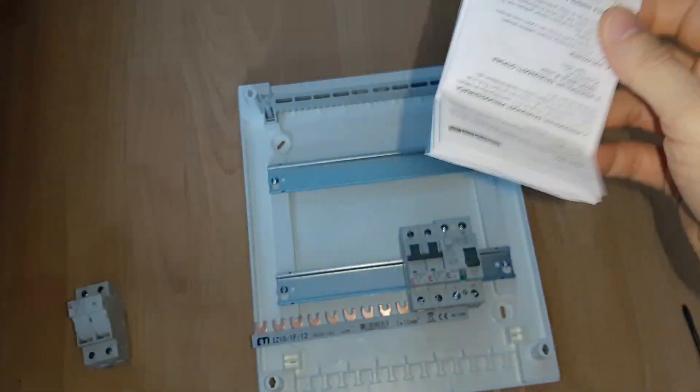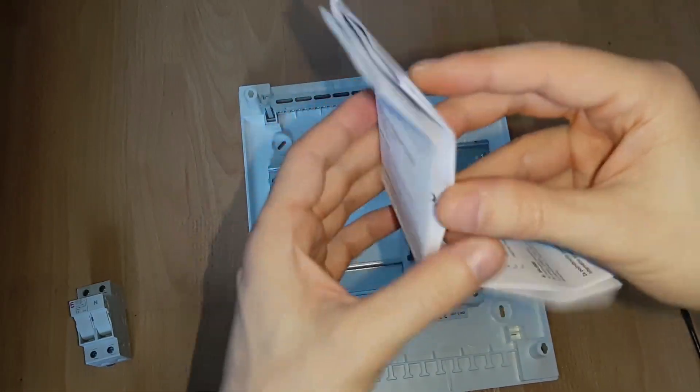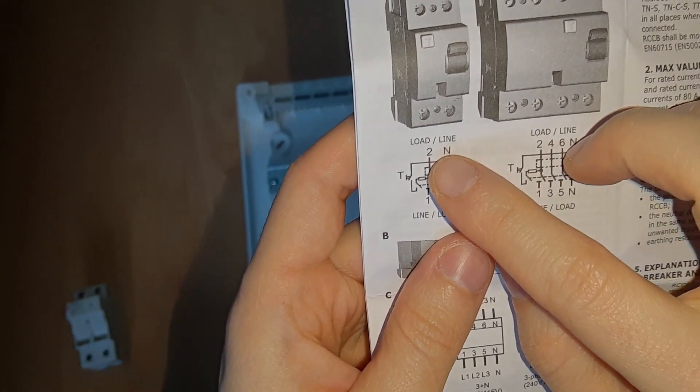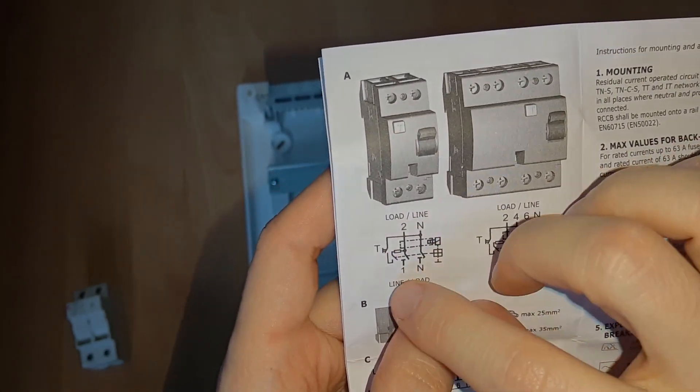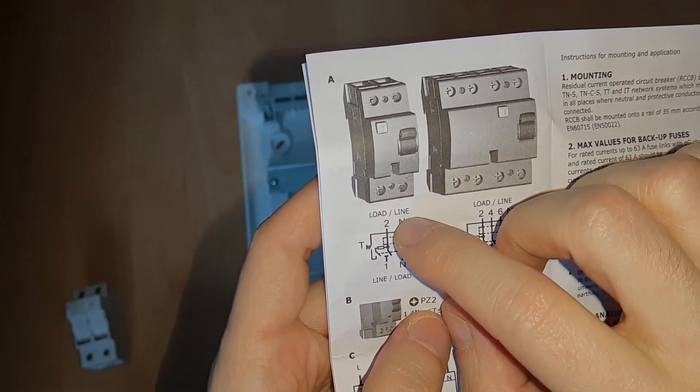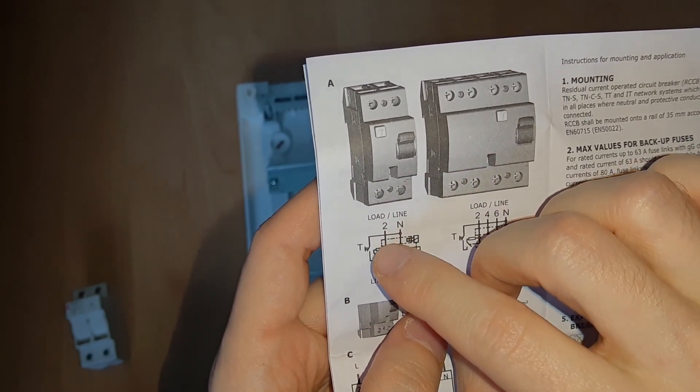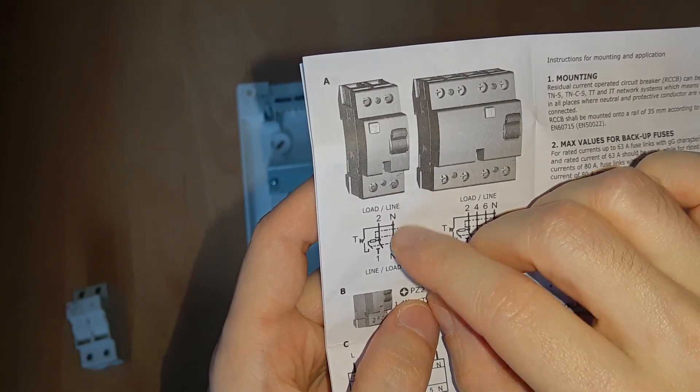So as you can see, you should make the connection on the bottom. I have the instructions for the differential here in case you're wondering whether you should make the connection on the bottom or the top. It says load, line, line, load. So you can put it either way, either from the top the line or from the bottom. You either put the line down and the load up, or the line up and the load down.